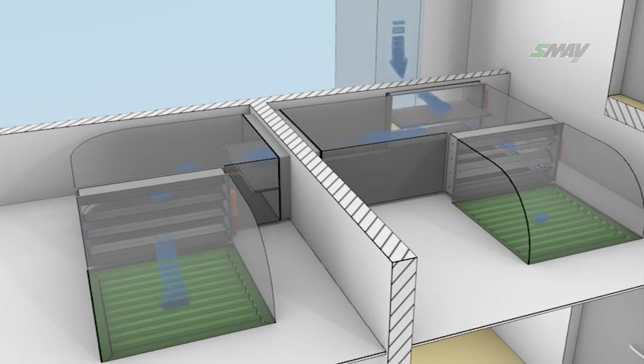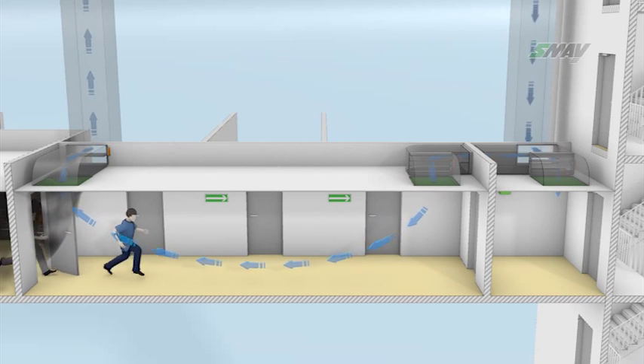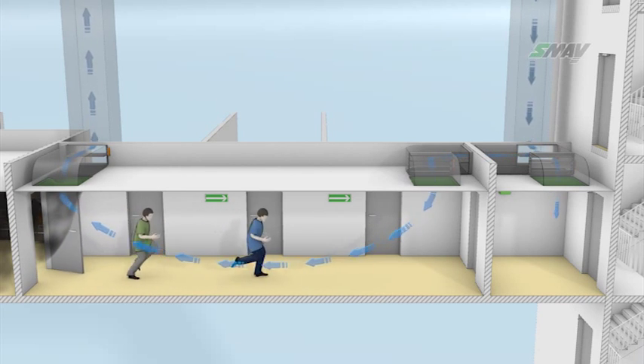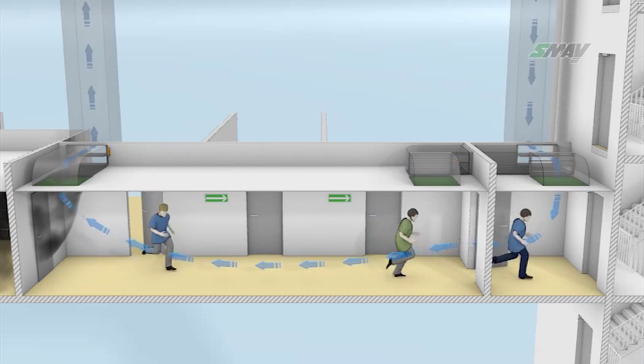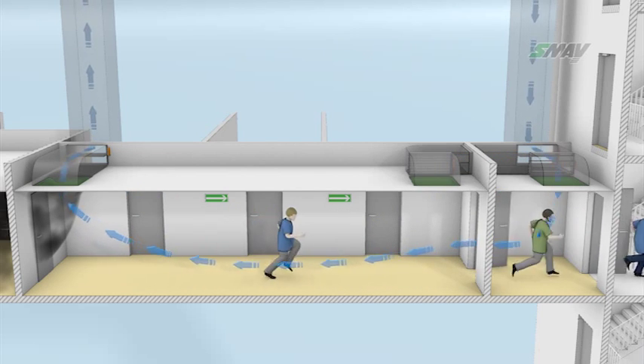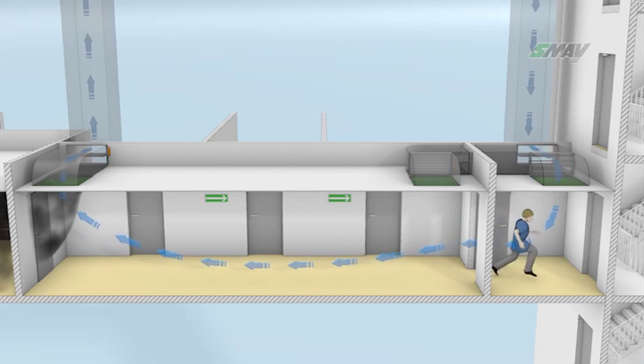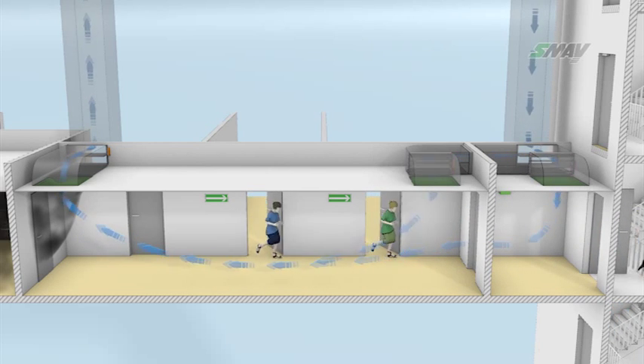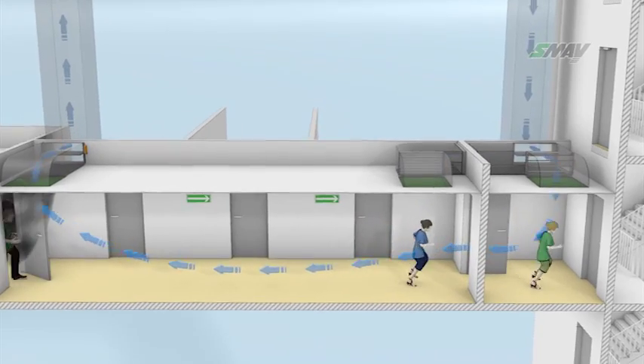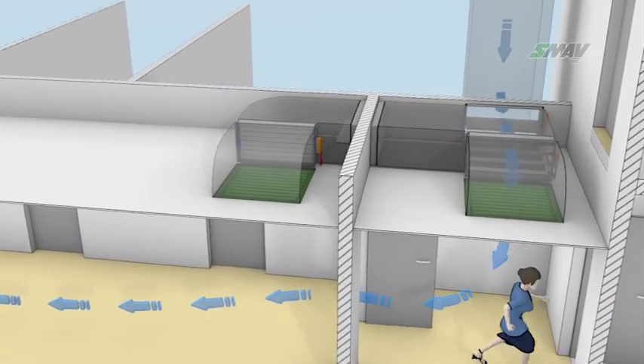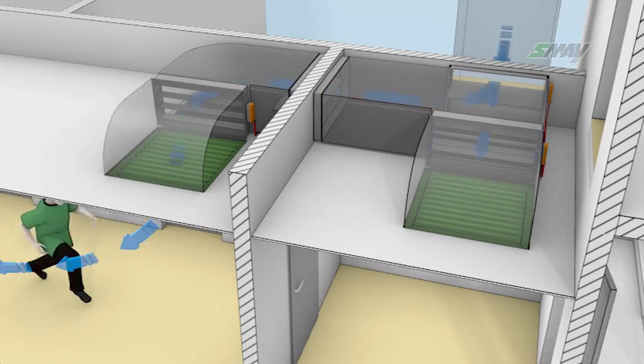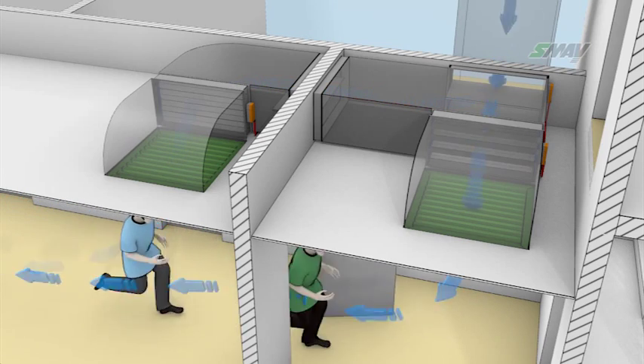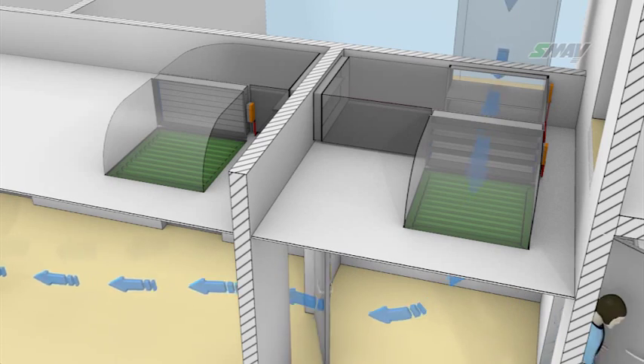When people begin to evacuate, doors between the lobby and the corridor are opened. When the doors are opened, pressure in the corridor and lobby will equalize, and this acts as a control signal for the system. This results in the damper in the duct leading to the corridor to shut, and the entire air volume is directed to the lobby. The air flows through the lobby doors into the corridor and is removed together with the smoke by the smoke extraction installation.